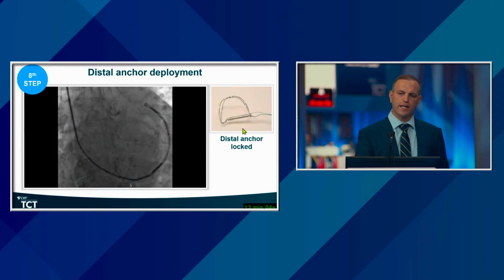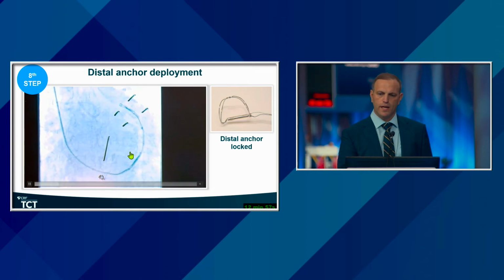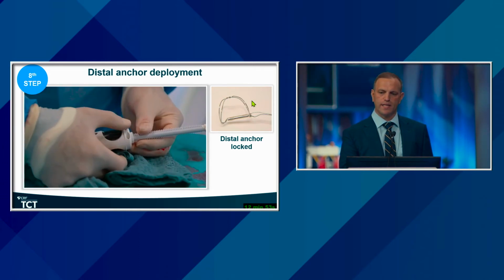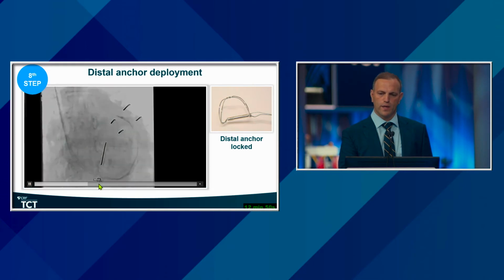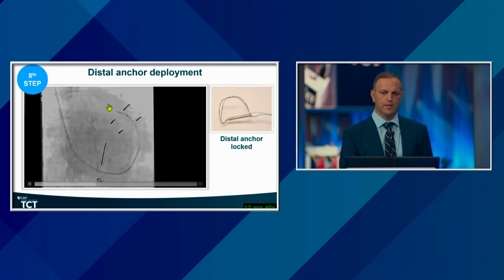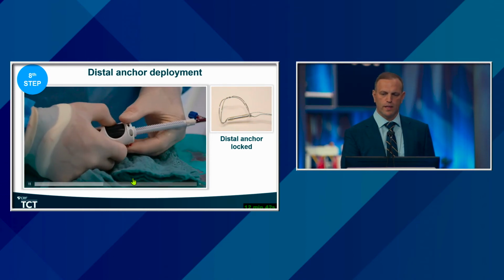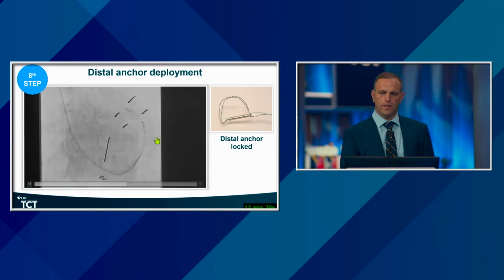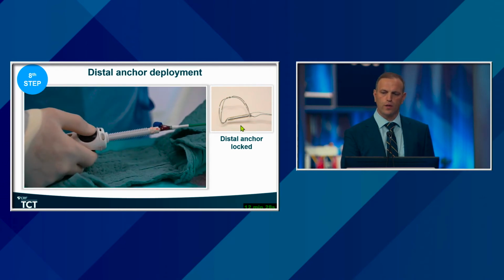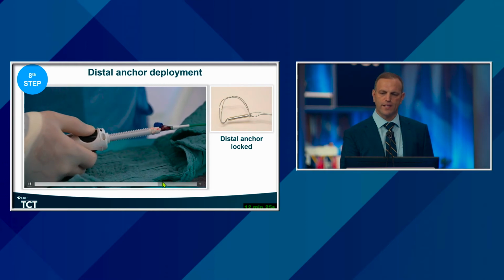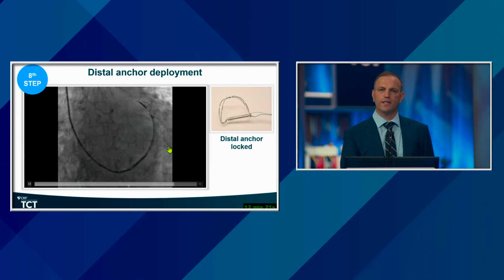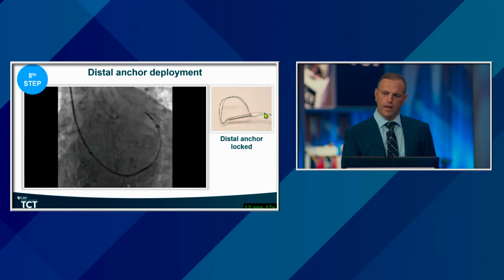That's the deployment of the distal anchor. Only turning the first knob in black arrow direction, and that puts out the distal anchor slowly. This way, it's going out slowly. It's a little bit too far, but it's no problem. We can pull it down slowly, and in this case we did it too. Pull it down slowly. Now the anchor is out here. And then we are going to lock the anchor by turning the first knob in the white arrow direction. That pushes the delivery catheter into the anchor, and this part is going over the diamond shape, and the anchor is locked now.